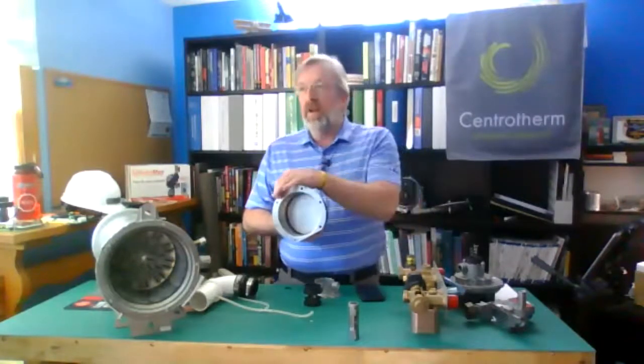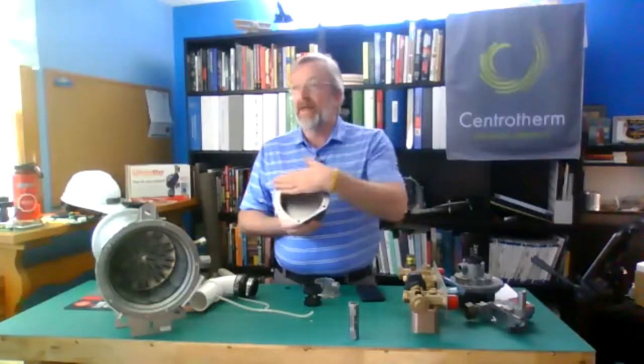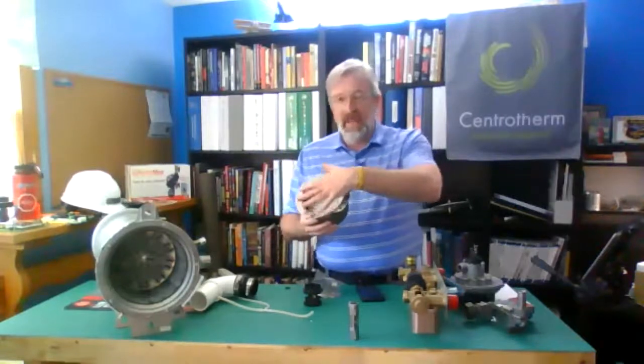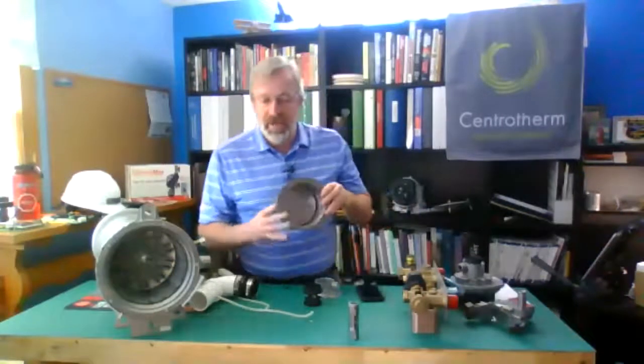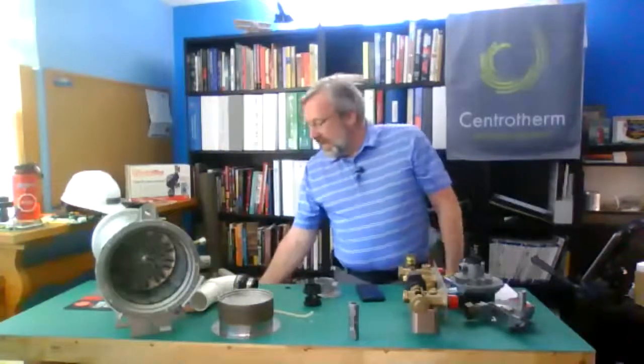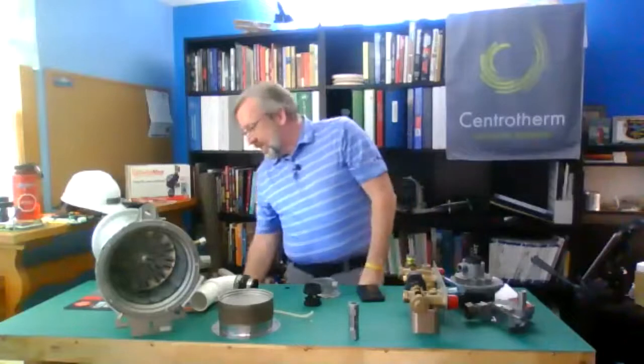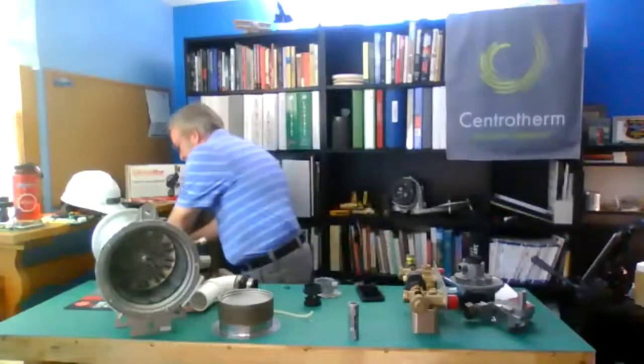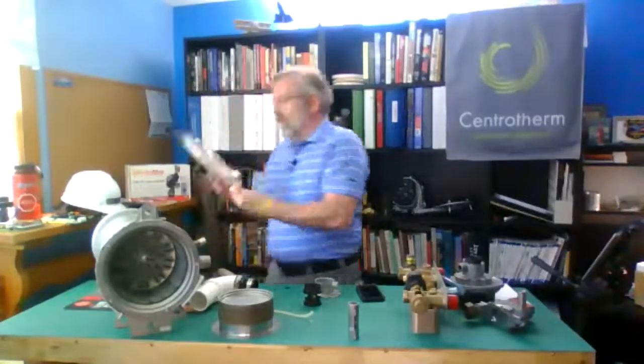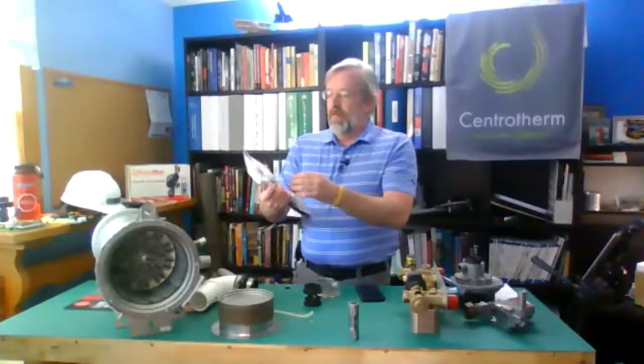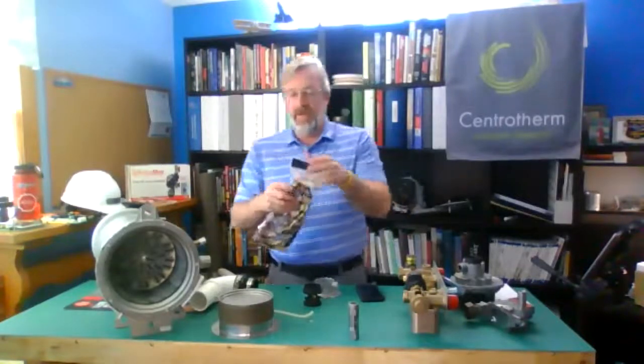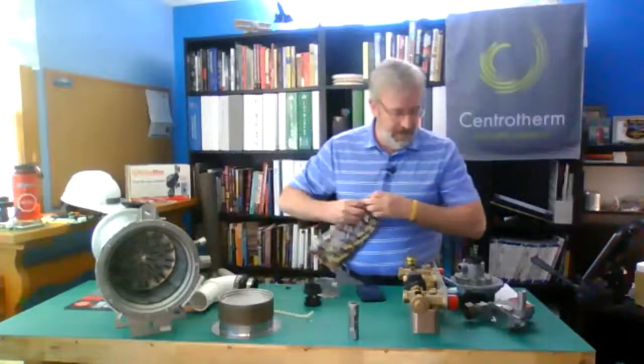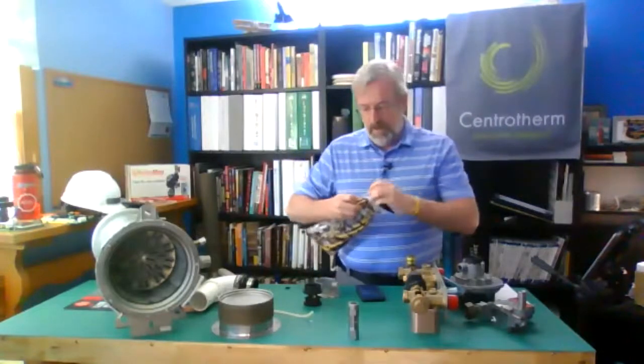If you've taken it apart, you're going to replace this gasket. Absolutely. This gasket won't be salvageable. That's the hot spot, and that's what that burner area is going to be subject to. So get it all back together. We put it on. Now, once we have it back together, we really want to pressure test it at that point in time. I don't know if my cable here's got that. It does. Perfect. All right.